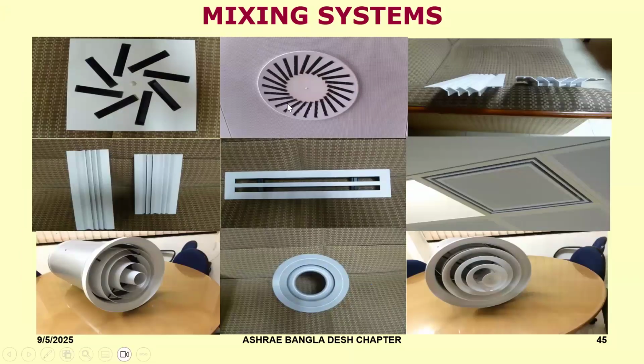Some more outlets which go on the ceiling. These are what we call slot outlets. These are outlets which you will use in large open areas where you want to throw the air over very long distances. The important thing is to understand the geometry of each of the outlets, understand how the air exits these outlets and how it performs in the space, and you must do the selection based on the performance characteristics of each of these outlets.